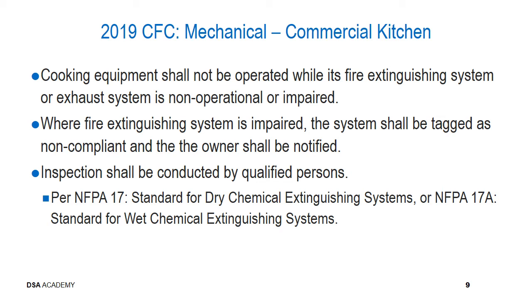Note that plans often utilize the word Ansul for a wet chemical extinguishing system. Ansul is a manufacturer of fire protection systems. It is not a system. There are many manufacturers, each with their own design and installation criteria. It is important to follow the manufacturer's installation, inspection, and test manual to achieve compliance.